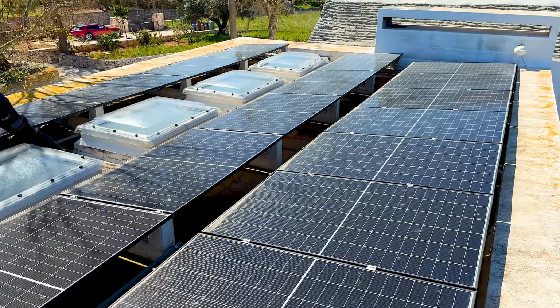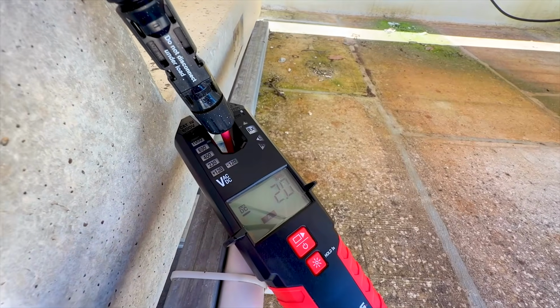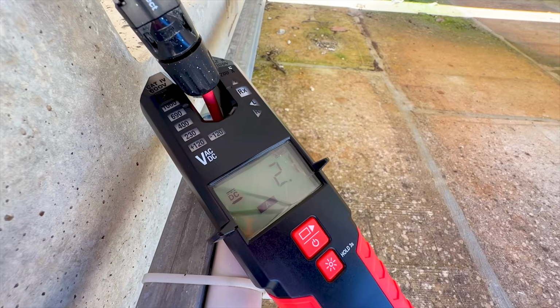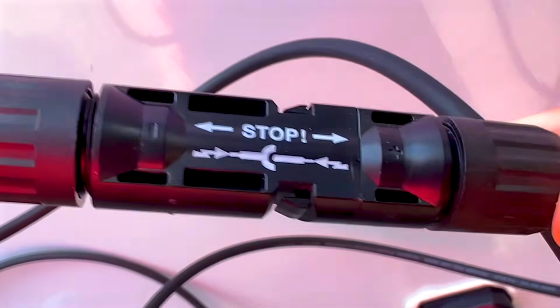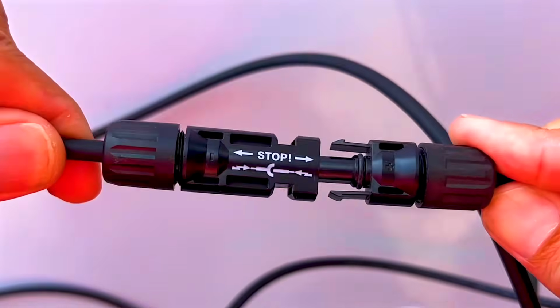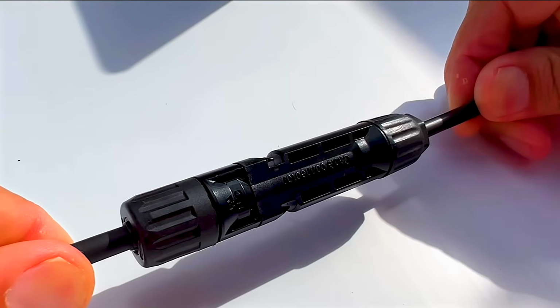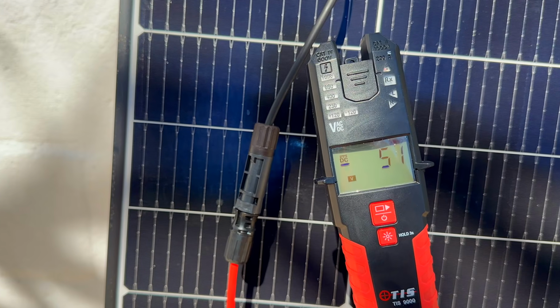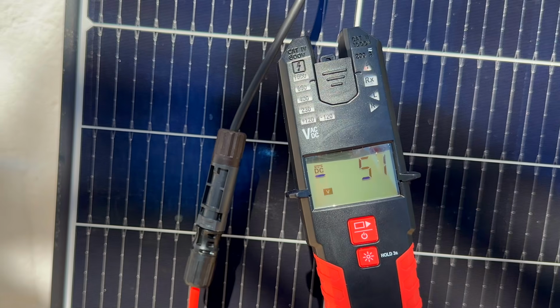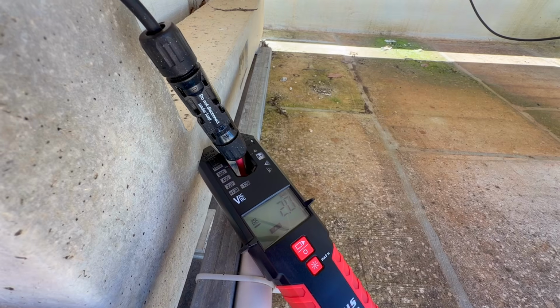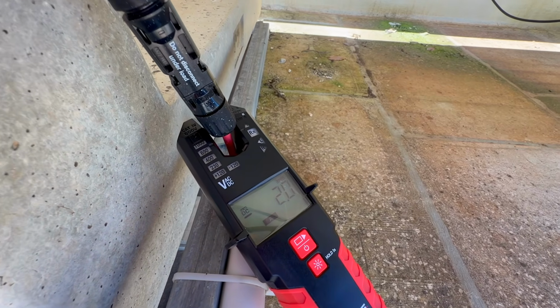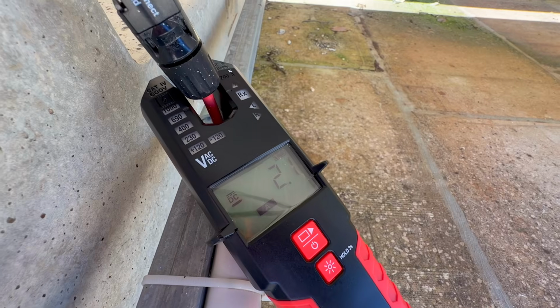A solar panel might look harmless, but under load, that MC4 connector is carrying live DC. Pull it apart at the wrong moment and you're not just making a mistake, you're creating an arc that won't let go. Now here's the problem. How do you know if current is actually flowing? With this new TIS9000 open jaw multi-tester, there's no guesswork. We can clamp straight onto the conductor, and right now we're seeing around 2.4 amps flowing through this string.